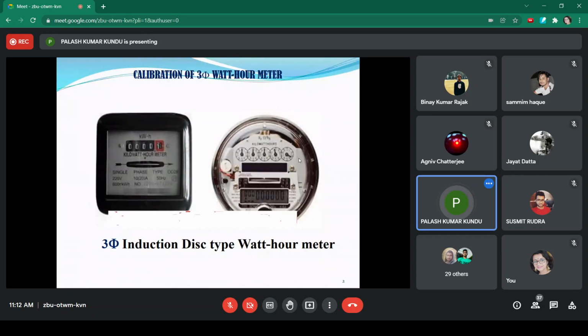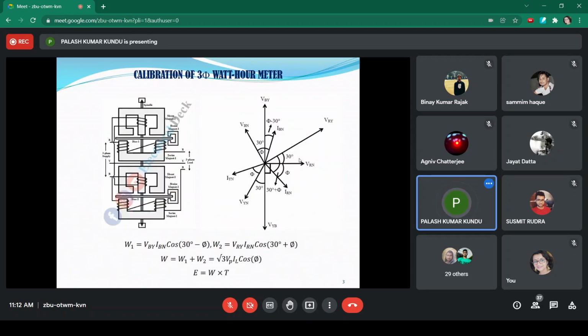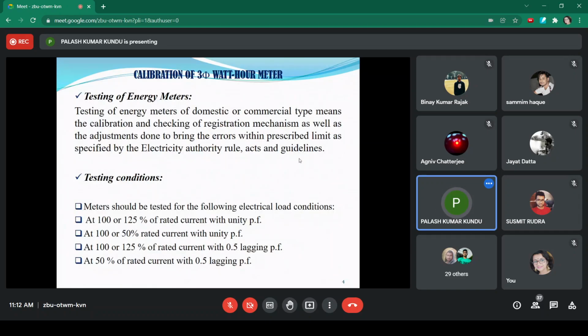So that's why the testing of the energy meter requires the calibration of the meter constant with the help of a proper calibration experimental setup: how much is the specified meter constant, compared with the value obtained experimentally, and what is the percentage error of the meter constant.